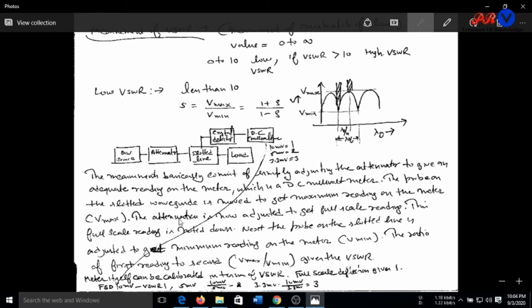Now again the attenuator, this one, is adjusted to get a full scale reading, so that we get the full value of voltage in this device. This is known as the full scale reading, which we have to note down. Next, in this way we can get this value. V max is calculated here.